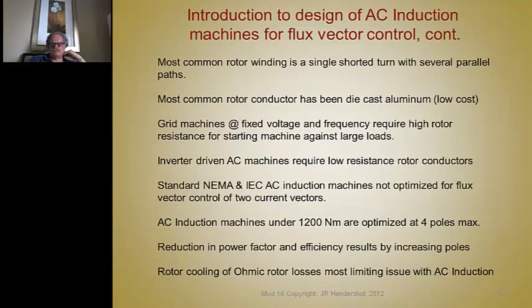But the problem with that is if you have a high resistance rotor, when you're up at rated speed, the heating and the losses in the rotor are so high that it gets very hot and it affects your continuous efficiency. So what you really want is a rotor that has high resistance during starting and lower resistance during running. That dichotomy, that characteristic of induction machines, dictated how the rotors were designed for the last 100 years. But that problem goes away when you drive it with inverters, and we'll study that in more detail and say that over and over again several times. Standard NEMA and IEC induction motors are really not optimized for flux vector control or control by two current vectors. They're optimized to give good starting torques and good running efficiencies with constant grid frequency and voltage.